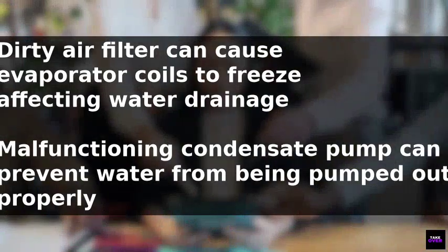A dirty air filter can also cause the evaporator coils to freeze, affecting water drainage, so it's essential to inspect the air filters regularly and replace or clean them with water as needed, ideally making this a monthly routine.